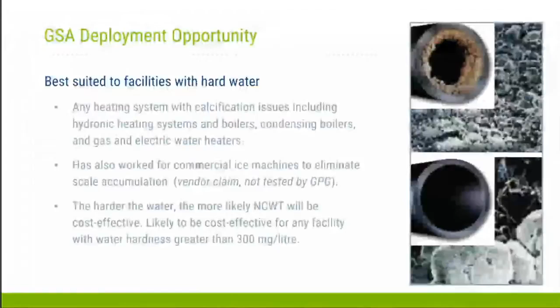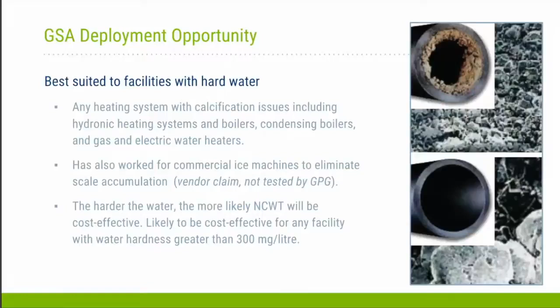The lessons learned to share with anyone who's considering using this system: sizing the device is key. As I said earlier, we first ran into problems where we thought the device might be a failure because the heating elements were still burning up. It turns out that measuring flow is really important. It's worth it to put an ultrasonic flow meter on whatever system you're thinking about using it on to make sure that your device is sized properly. Don't just use what is shown in the mechanical drawings. Also, and this is a side note, if you're using an electric water heater, make sure you're using commercial grade elements.